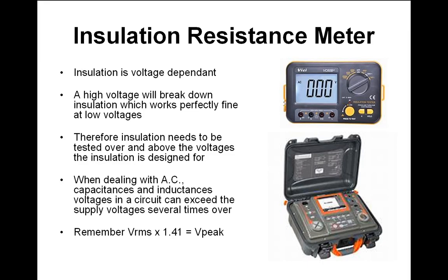Okay, Callum, I'm going to talk about this later as well. I'm just looking at the chat room. Callum says, we used to blow up fuses in them all the time at college by having them on the wrong settings when measuring things. Yeah, that's when we look at ammeters. We're just looking at DMMs. When you measure voltages and you've got your meter wires connected to the correct terminals, which would be common and V for voltage, everything is fine. But as soon as you go to common and then A for ampere, it's almost like a straight piece of wire. If you put it across a power supply, you'll blow the fuse straight away. So we're going to talk about this tomorrow in a bit more detail.